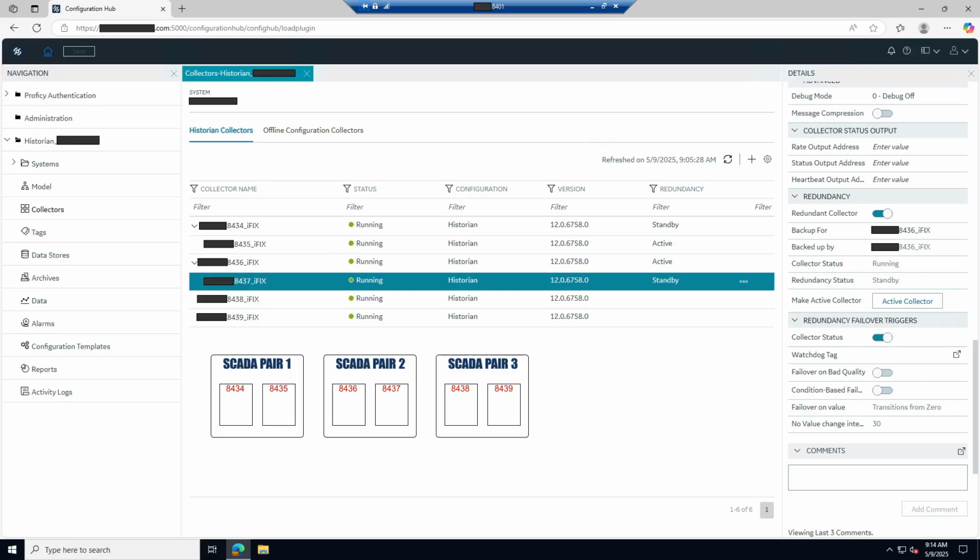In this architecture, iFIX is set up with Enhanced Redundancy, which means there are 2 iFIX nodes for each redundant server pair. For every pair of iFIX nodes, if one server goes offline or into maintenance, the other server continues serving data to client HMIs without interruption.